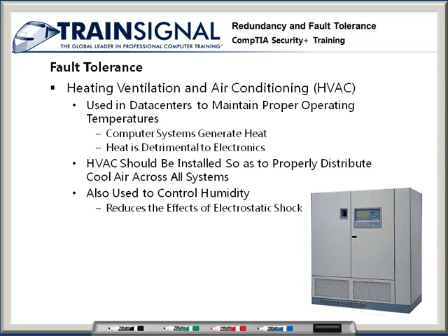And I tend to like to recommend to my customers that they're using between 40 and say 70%. I believe that 40 at the low end is a good number, because any lower than that and you do start getting into ESD issues. And then again, at the high end, I think 70% is still reasonable, and I wouldn't want to see it getting much above that.